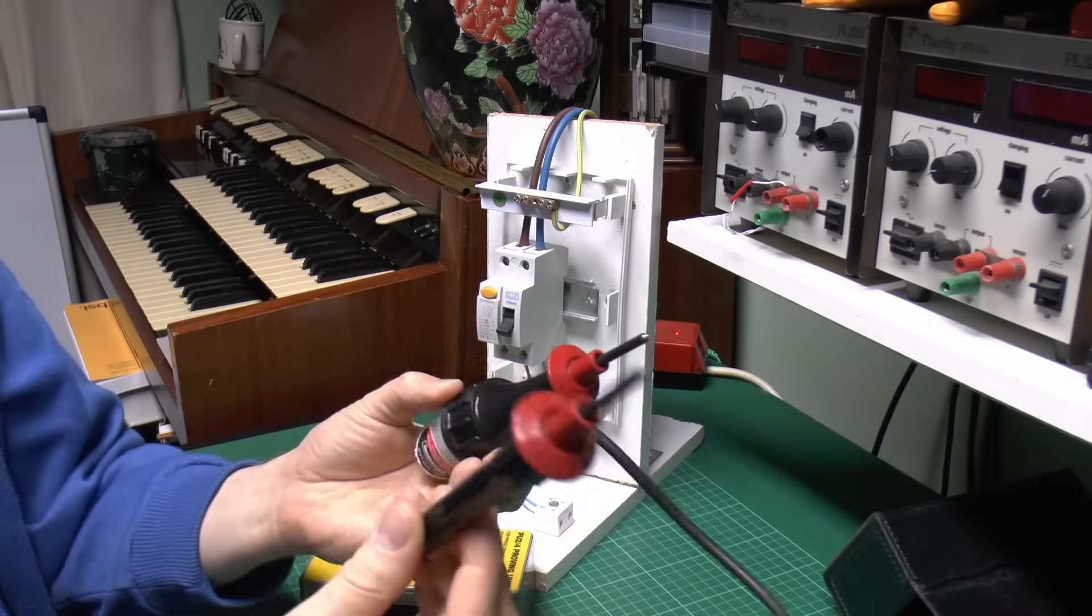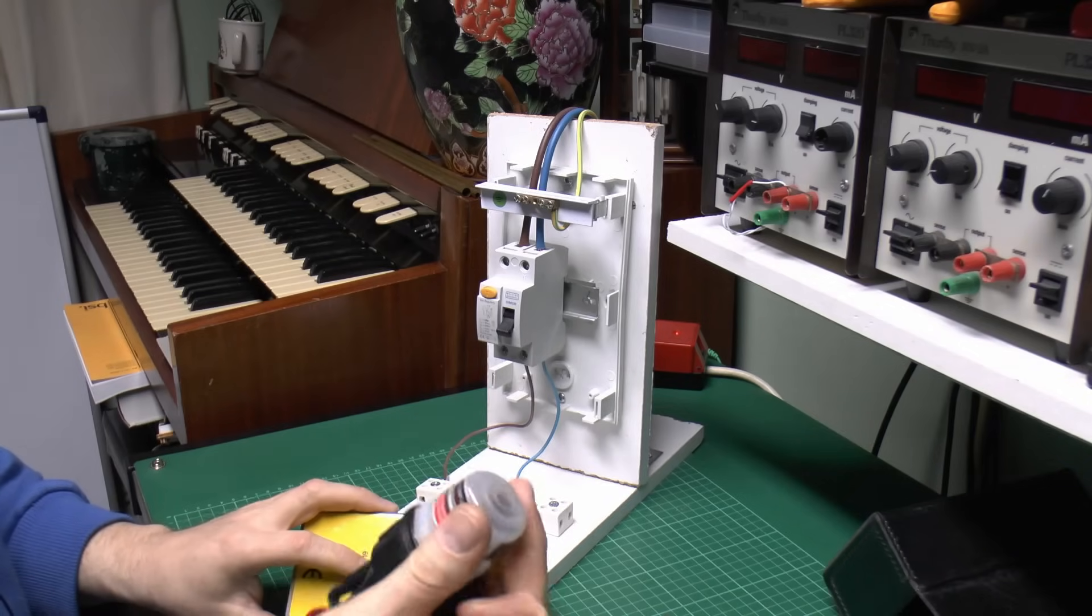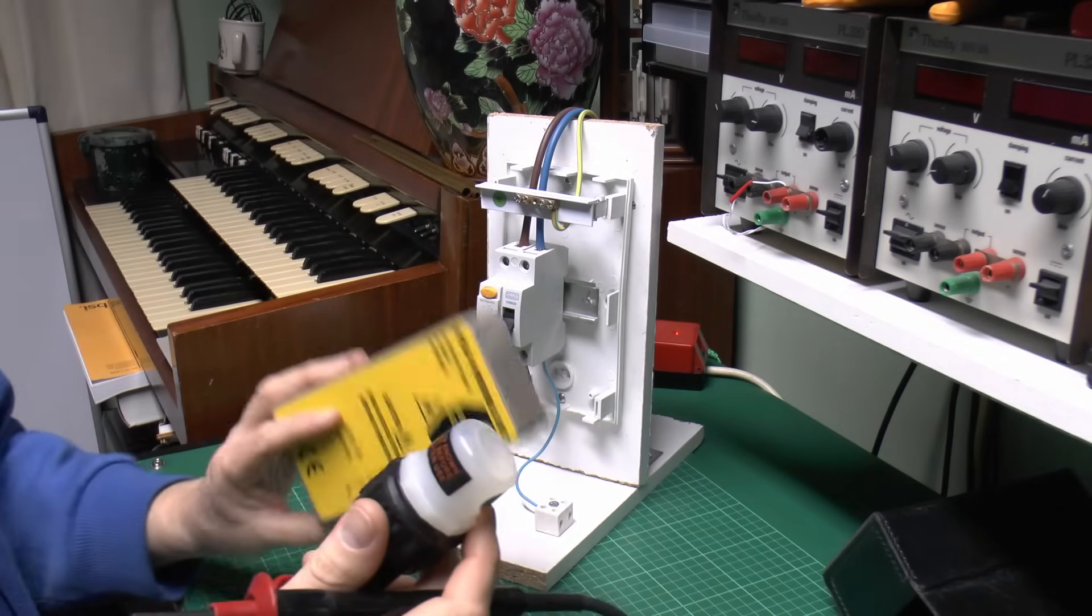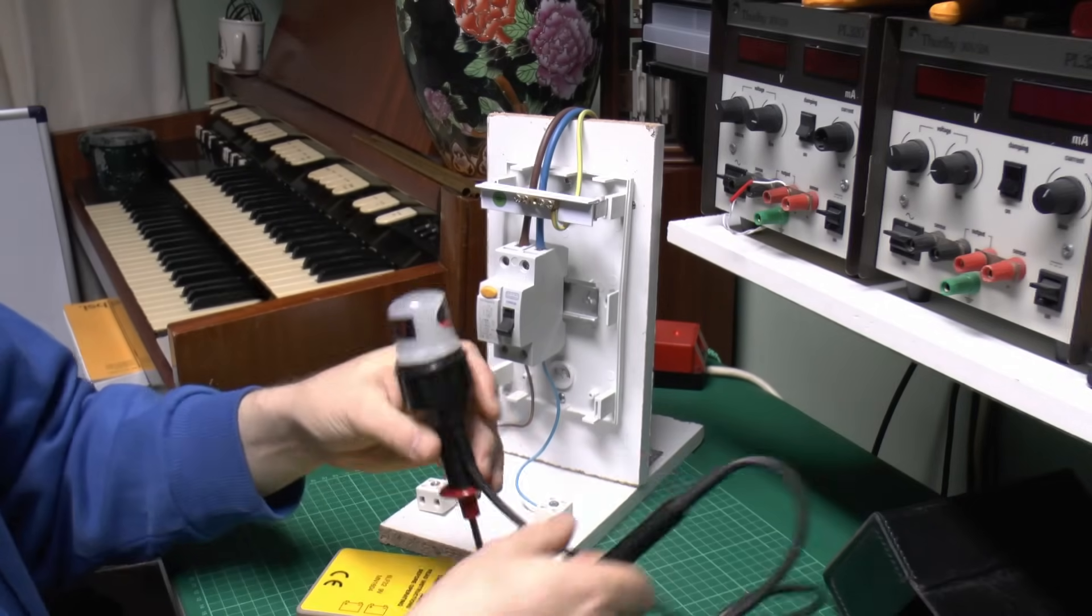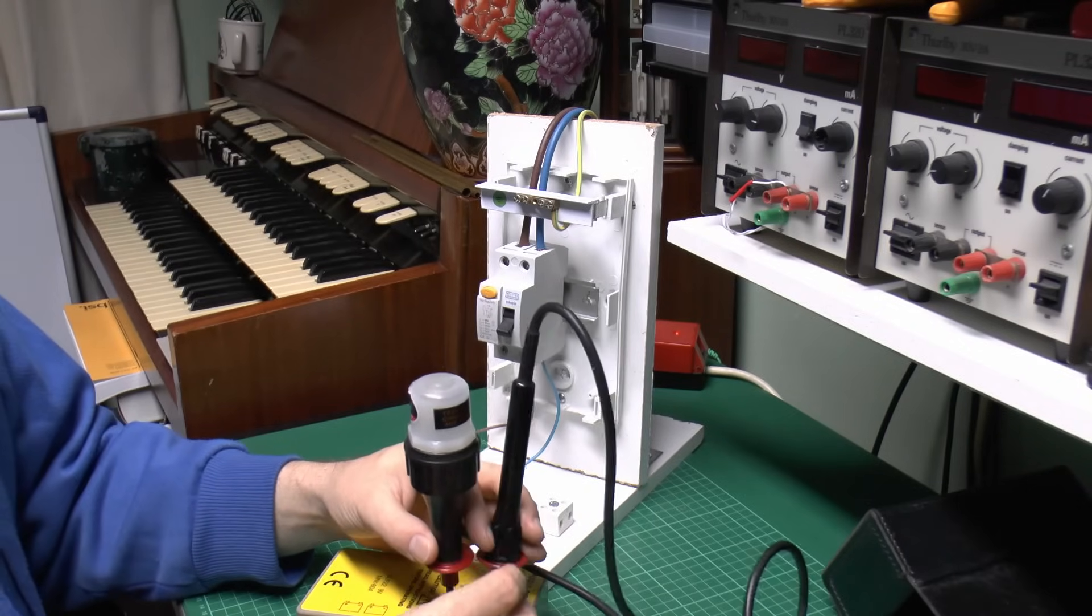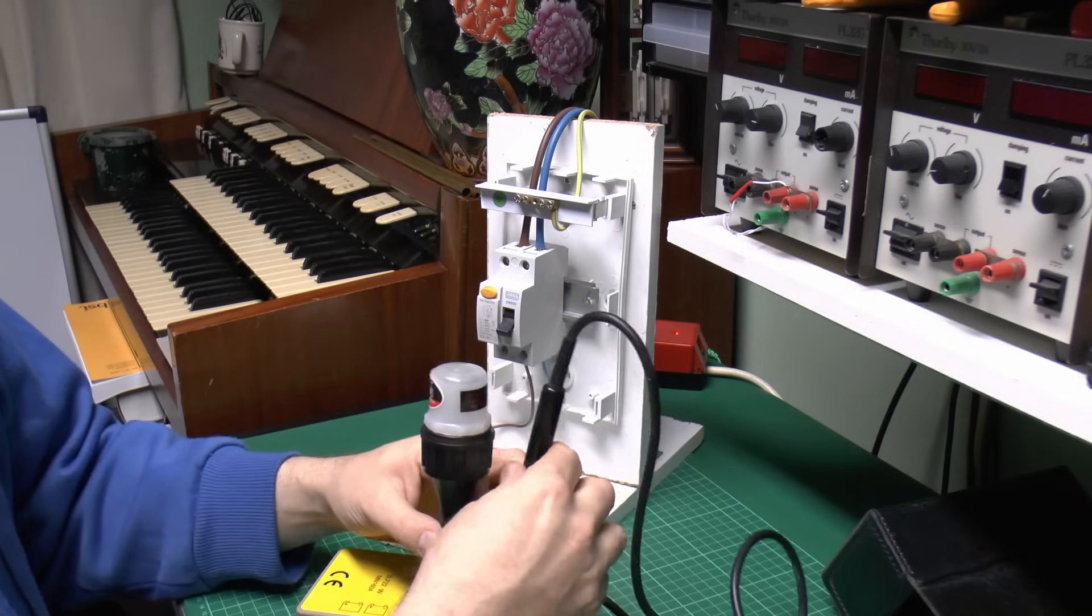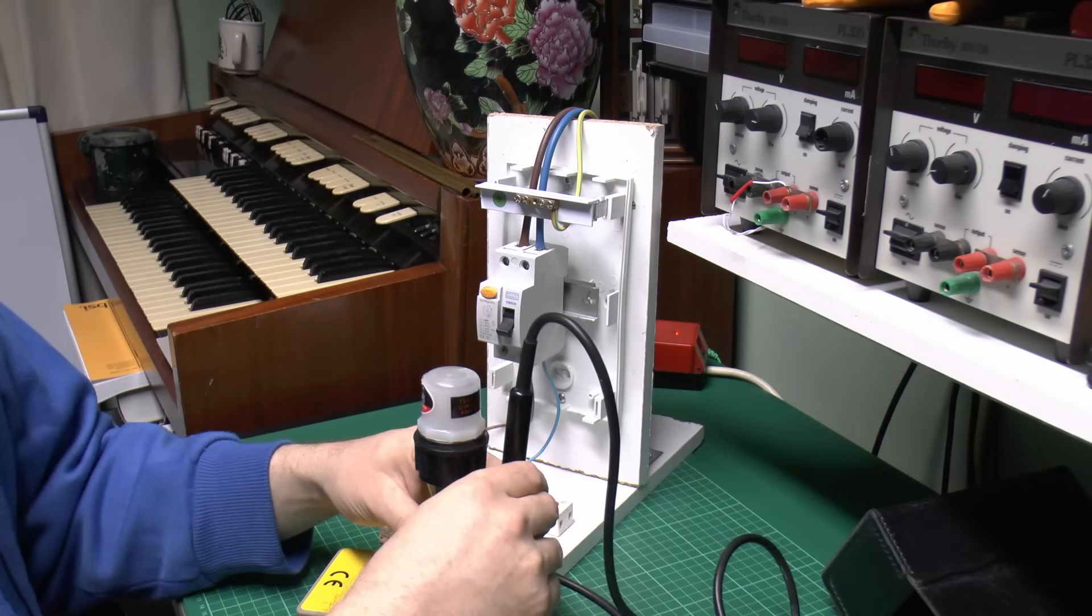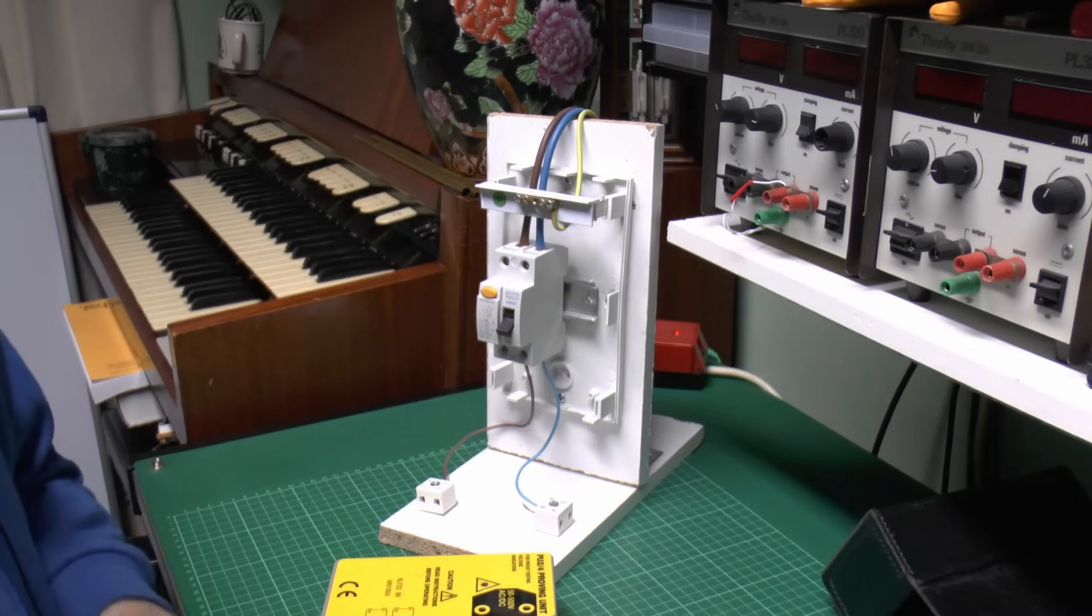And exactly the same situation would apply with this particular one, again with the lamp in there. Some proving units can't actually provide enough power to light these, this particular one can, and if you're going to buy one of these and you've got these of course make sure that this does provide enough power to actually light this, otherwise you're not going to get very far, complete waste of time. I have to say this one does have the required power, so again I'll just press this in here, and I'll just mute the audio again because this creates a lot of interference on the camera, but again we'll see the lamp should illuminate at the top here. So there we go, that's how you would do those.